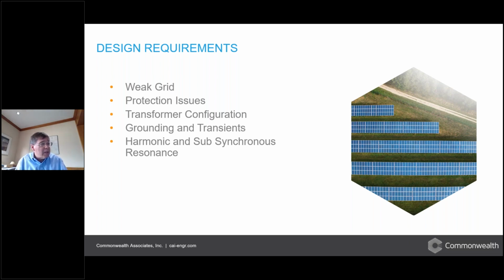And then that follows on, there are protection issues that need to be dealt with. You need to be sure that you're meeting the requirements that are found. There may be special configuration issues that you need, special relays that you want, particularly if you have a weak grid. You're going to have to concentrate on coordinating with the inverter controls to meet the requirements of PRC 24, PRC 27, PRC 19. Those are areas that are entirely in flux because, like I said, those standards that say how this should be done are heavily oriented to synchronous machines, and what you need to do on protection is in flux. And you'll see more of that in a practical way as we get toward the end of the presentation.